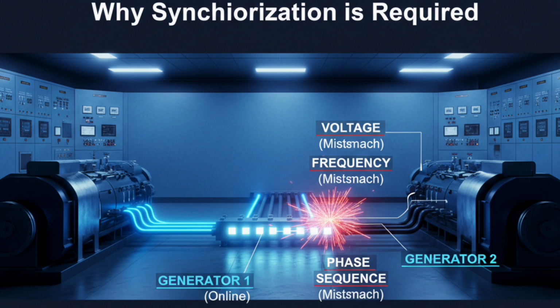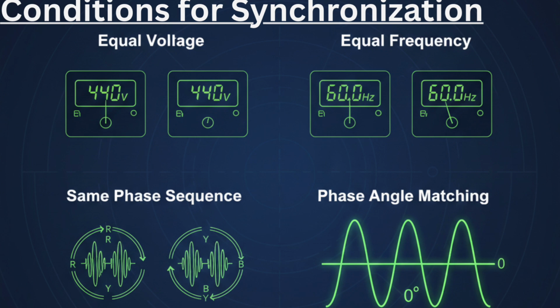There are four main conditions for synchronization. First, voltage must be equal. If incoming generator voltage is higher, it will push reactive power into the system. If lower, it will absorb reactive power. Second, frequency must be equal. If frequency is higher, the generator will try to take more active load suddenly. Third, phase sequence must match. If phase sequence is wrong, it can cause a short circuit condition immediately. Fourth, phase angle must be zero difference. That means both waveforms must align perfectly. When all these conditions are satisfied, we close the breaker at the correct moment. In manual systems, we use lamps or synchroscope. In automatic systems, PMS handles it electronically. Understanding these conditions is the foundation of safe parallel operation.